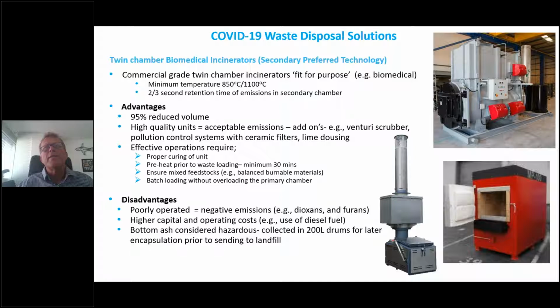Now, also what you need to consider is that incinerators probably have a higher operating cost than, say, autoclaves, which use steam, water and electrical technology. This is using diesel fuel for the burners. So the larger the incinerator, the more diesel fuel will be used, and the higher the cost. Also, you need to consider that any ash that comes out, even though it might be reduced to just 3 to 5% of the total volume that went in, should be considered hazardous waste because it was biomedical waste material. You should collect this and go through a process of what we call encapsulation, which is encapsulating that material into a concrete or sand cement mixture for later disposal at landfills. Next slide, please.